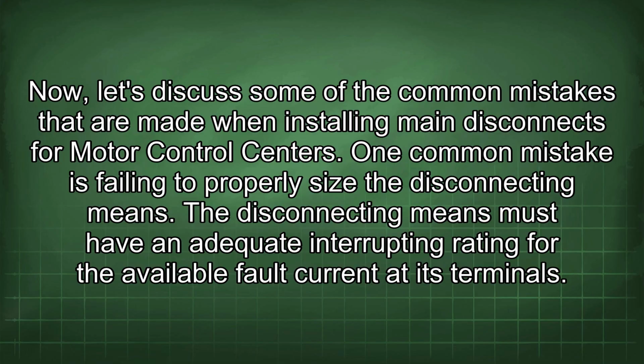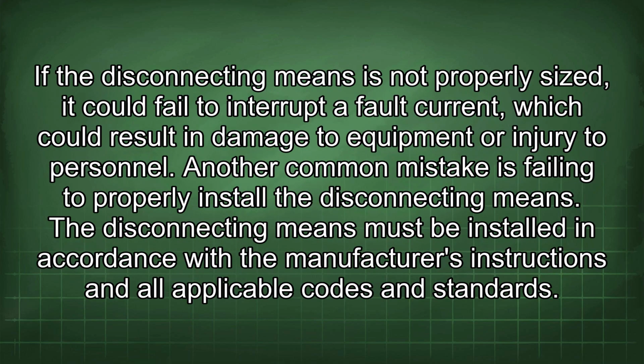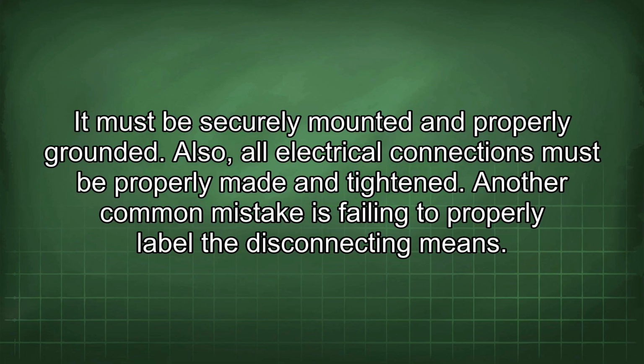One common mistake is failing to properly size the disconnecting means. The disconnecting means must have an adequate interrupting rating for the available fault current at its terminals. If the disconnecting means is not properly sized, it could fail to interrupt a fault current, which could result in damage to equipment or injury to personnel. Another common mistake is failing to properly install the disconnecting means. The disconnecting means must be installed in accordance with the manufacturer's instructions and all applicable codes and standards. It must be securely mounted and properly grounded. Also, all electrical connections must be properly made and tightened.